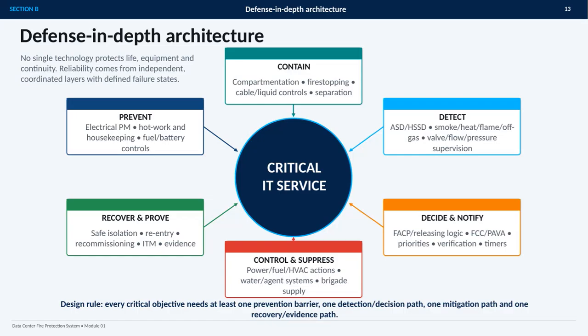This slide presents a defense-in-depth architecture for protecting critical IT services in a data center fire scenario. The central idea is that no single technology can protect people, equipment, and operational continuity on its own. Reliability comes from independent, coordinated layers, each with a defined response if another layer fails. The sequence begins with prevention, including electrical maintenance, housekeeping, hot work controls, and management of fuels and batteries. If an incident still develops, containment limits its spread through compartmentation, fire stopping, separation, and control of cables and liquids. Detection then combines air sampling or high-sensitivity smoke detection with heat, flame, and off-gas monitoring, along with supervision of valves, flow, and pressure. Next, the system decides and notifies.